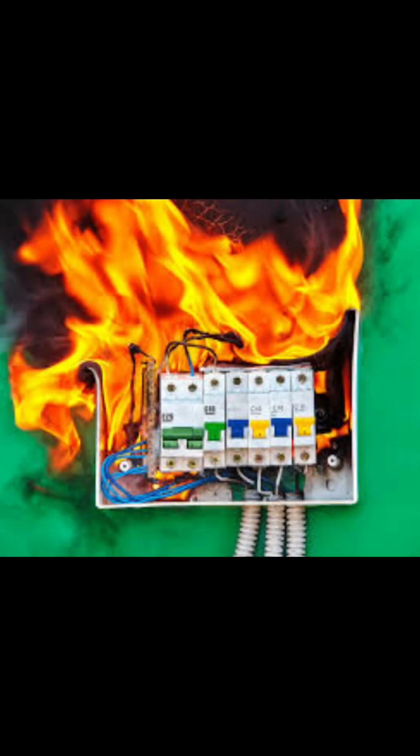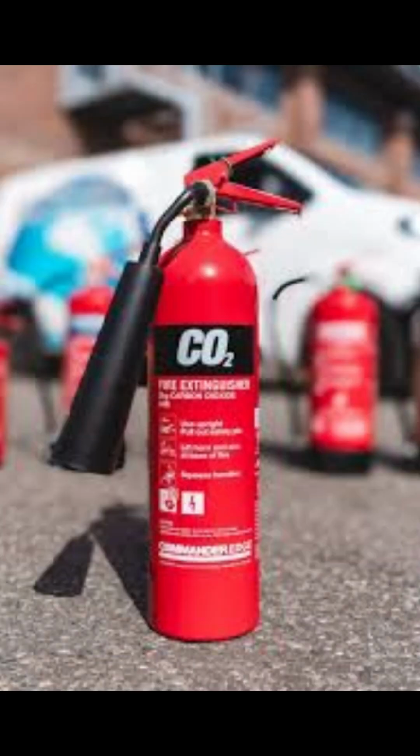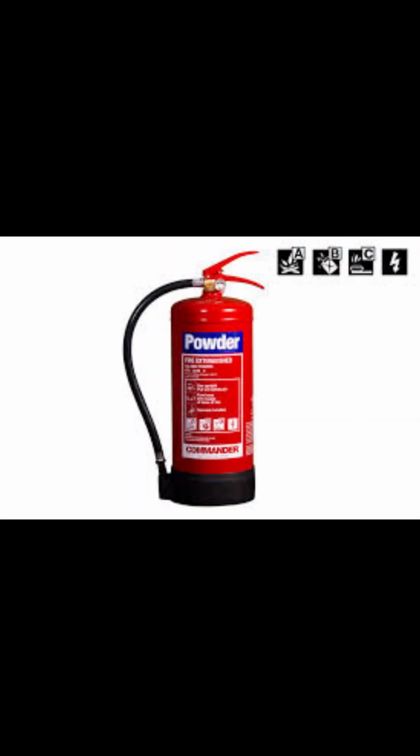Electrical fire: these occur in energized equipment such as panels, machinery, and computer systems. Water conducts current and creates electrocution risk. Use carbon dioxide or dry powder extinguishers only. Your extinguisher selection is not a preference, it's a technical requirement.